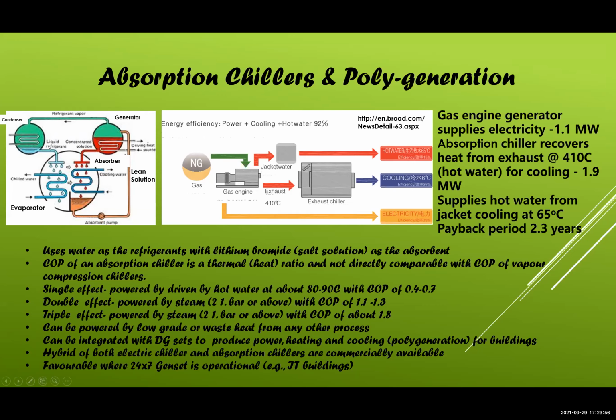The advantage of that is it works on heat rather than power, and therefore you can use waste heat to run an absorption chiller, and the waste heat can come from even a gas engine or a generator, diesel generator. So by cooling from the exhaust of the gas engine, you can recover heat and run a chiller to produce cooling. Then the jacket can be cooled to produce hot water. The engine will produce electricity. So we call it tri-generation. It produces electricity, cooling, and heating.